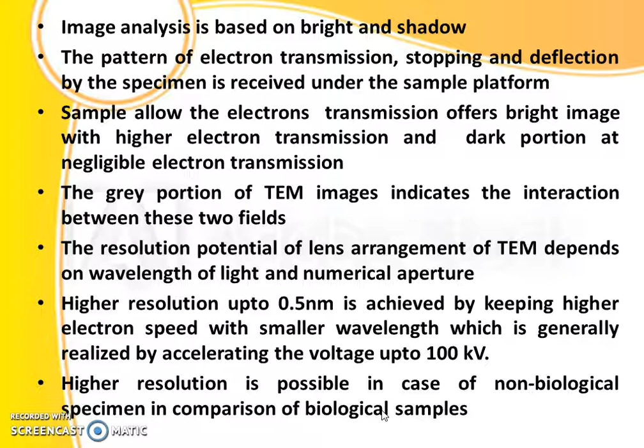The resolution potential of the lens arrangement of TEM depends on the wavelength of light and numerical aperture. High resolution up to 0.5 nanometer is achieved by keeping a higher electron speed with a smaller wavelength, which is generally realized by accelerating the voltage up to 100 kilovolt. And nowadays different TEMs are available in which voltage can be accelerated up to 300 kilovolt. So high resolution is possible in the case of non-biological specimens in comparison to biological samples.